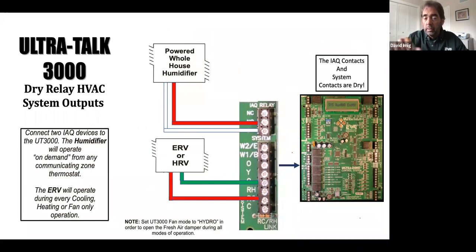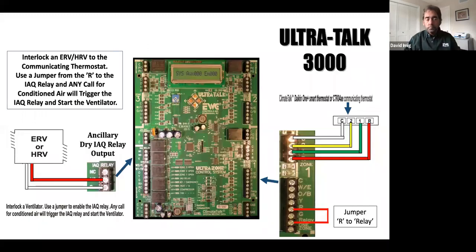Another application, again, that we need to see a demand from the zone thermostat to utilize operation of the humidifier, and we need to see a heating, cooling, or fan call to utilize the ERV, HRV. If we are just using the IAQ relay and I want to communicate to that, this is just an example showing that I am tying in the communicating or programming the communicating thermostat to trigger the IAQ relay and start the ventilator.